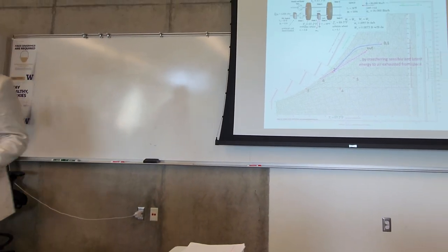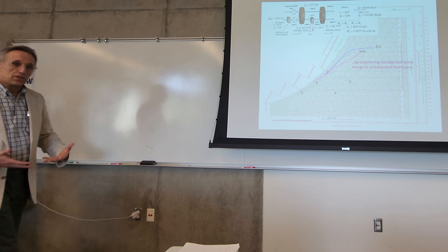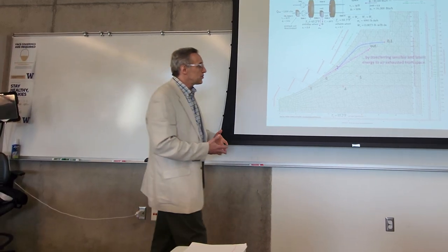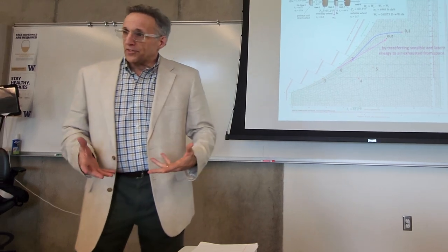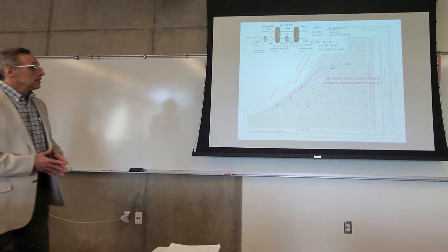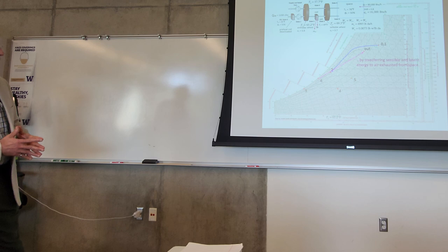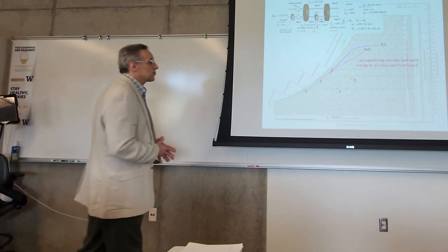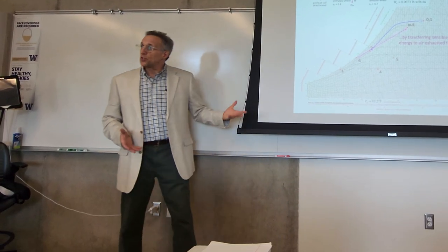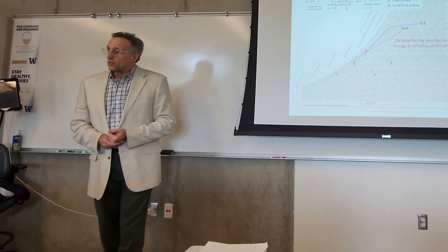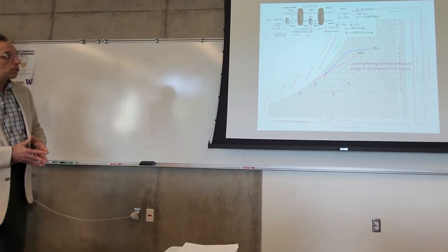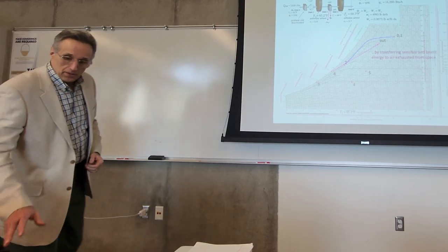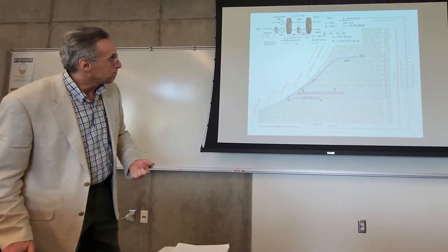That's a lot of cooling without adding any energy, you know, without refrigeration or some kind of active mechanical. We do need fans. And you can see the fans there. And these systems do have significant pressure drops. So it's not cheap. So you really have to be careful in doing the economic analysis to make sure that this is going to be feasible, and you're actually getting an economic benefit from it.